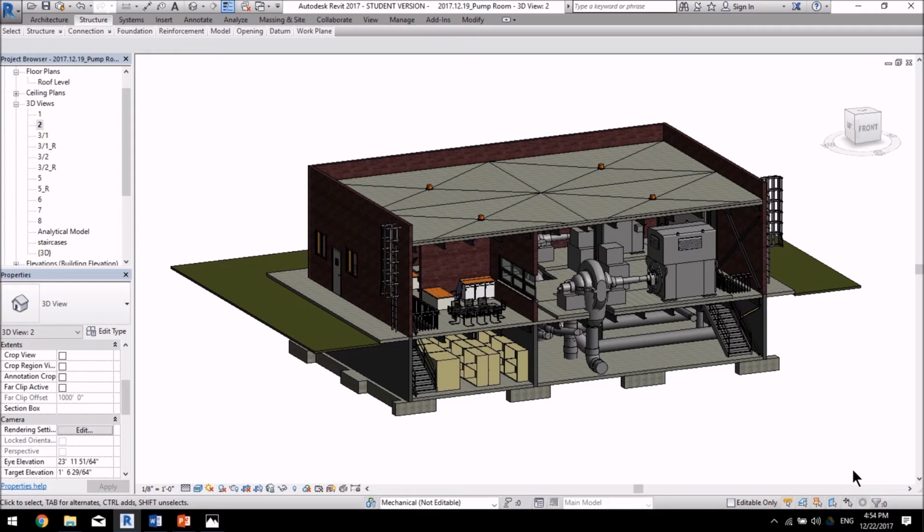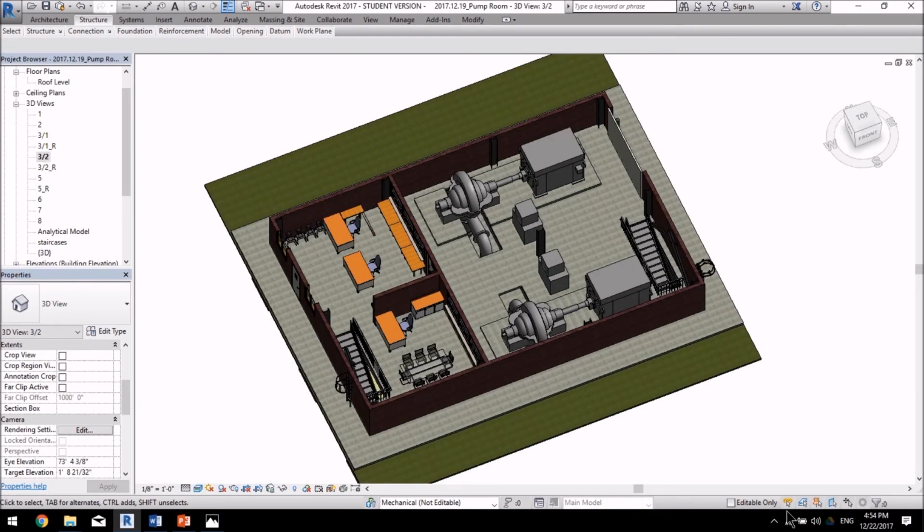At the time of the incident, the firefighters had to use this door to make their way to the storage room through the office area. Since the building was under operation at the time of the incident, as you see in the model, the office area was full of furniture and consequently slowed down the firefighting process and eventually led to more damages in the building.